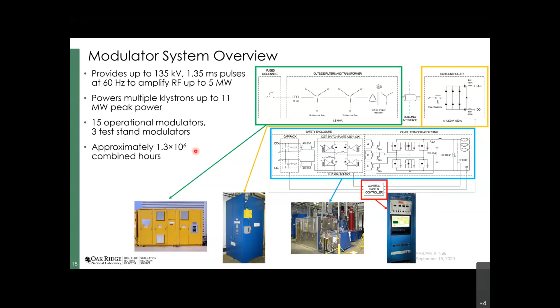So, breaking down each of the major subsystems, this is the power transformer. The power comes in over here on the upper right at 13.8. It goes through a line reactor, which provides the impedance match and some harmonic mitigation. Also, because we're driving a 6-pulse system, we create a lot of 5th and 7th harmonics, and we wanted to stay below the IEEE 519 requirement. So we added a 5th and 7th harmonic trap to the system, and it is quite effective. You can see down here with and without the traps: red is without, and black is with the trap. You can get up to about a factor of 3 reduction in those harmonics.